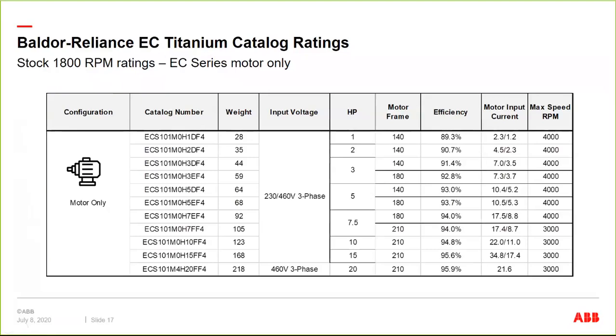And all of these can be run above base speed. For example, a traditional electrically commutated design, and this is just a technology limitation, it's not just me making a comparison, DC machines aren't going to run above base speed, so they're limited to base speed or below. The advantage of this being an induction motor is we can run into the constant horsepower range. So if you have an 1800 RPM motor up to a 180 frame, we can go to 4000 RPM, and then a 210 frame up to 3000 RPM.